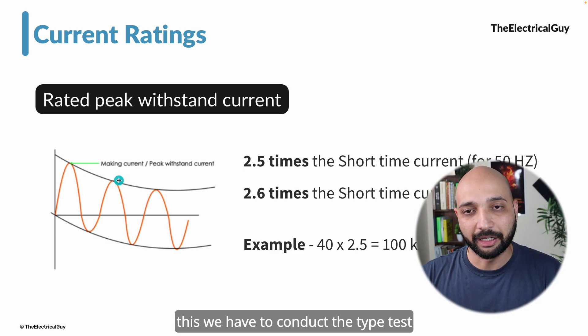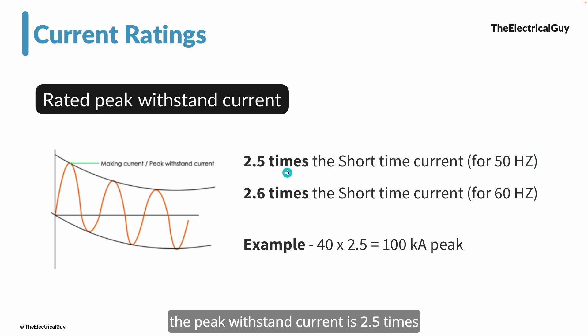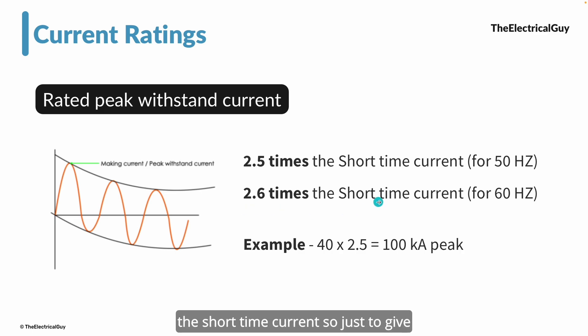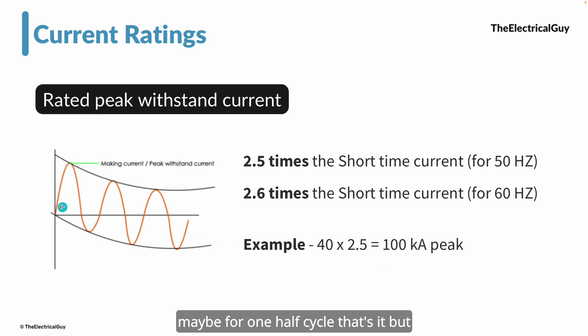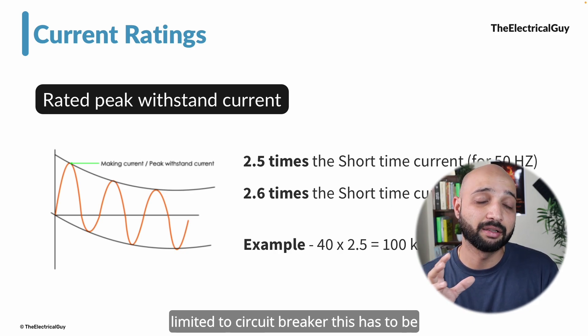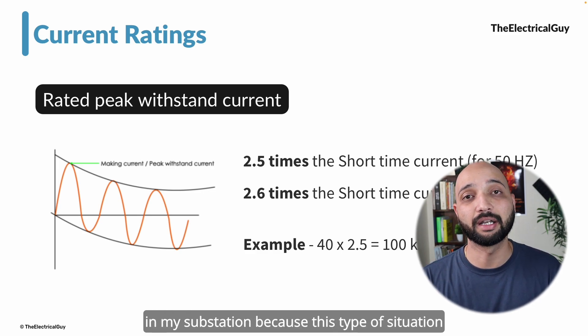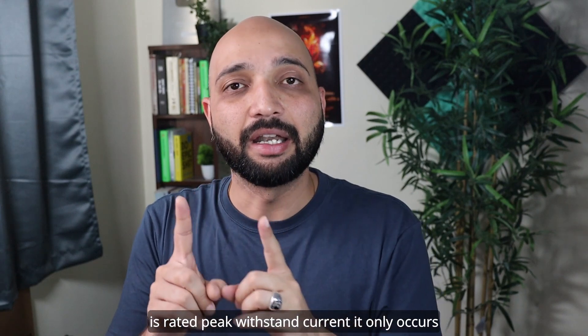To prove this, type tests must be conducted on the switchgear. Based on industry experience, IEC states that this current does not go beyond a certain limit. If the system operates at 50 Hz, the peak withstand current is 2.5 times the rated short time current. If it is 60 Hz, it is 2.6 times. For example, if the short time current is 40 kilo ampere, then the peak withstand current would be 100 kilo ampere. The switchgear should be able to carry this for a limited time — not specified by IEC because it is very short, perhaps only one half cycle. This rating is not limited to circuit breakers; all switchgear and devices connected in the substation must meet this requirement.